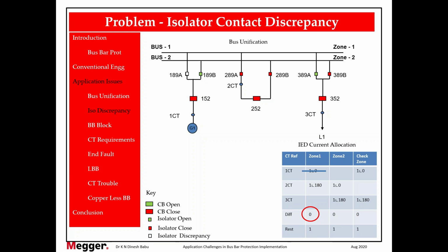In that kind of situation, we discussed the directional principle earlier. The directional principle will check the direction of all the bays. So during a healthy condition, if one isolator status is missing, there may be other bays which have more currents at 0 degree and 180 degree. The bus bar will trip only when all currents are at 0 degree. Even if 1 or 2 currents are at 180 degree, it will not permit tripping. In that scenario, for this isolator discrepancy, the main zone will not pick up in the directional condition. And even if it picks up, the check zone will not allow operation because the check zone has not picked up.